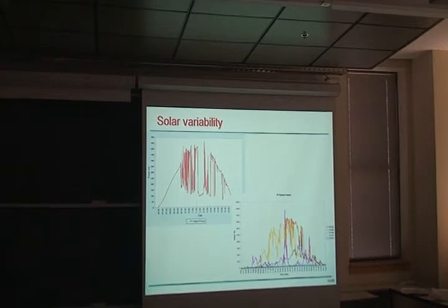So just to clarify, I thought most houses have voltage regulation so that the maximum power set point can't cross certain limits. Are you talking about when the power starts feeding into the grid that you start getting these issues? No, so it's a passive design at the moment. The utilities say, okay, we're going to have this many houses. That implies an average of each house has a certain amount of load, and then they'll look at what voltage drop that will induce along the line.